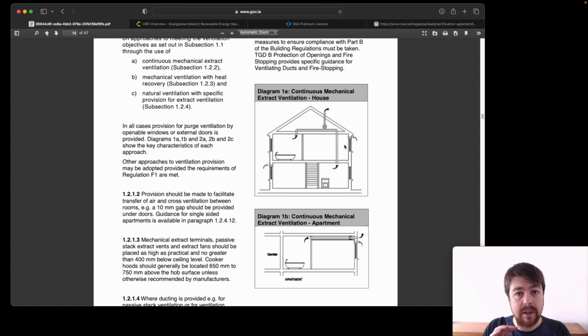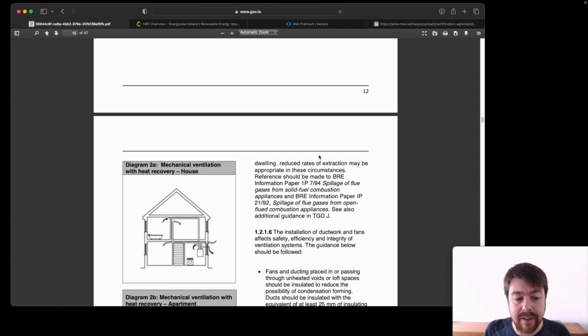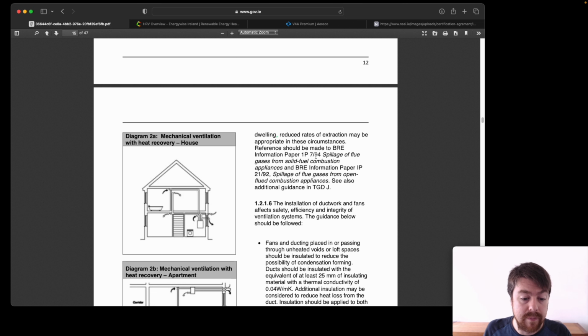But I want to do something a bit smarter, and for that I want to look at a mechanical heat recovery ventilation system. The idea, quite similar to what you'd see in a lot of North American homes, is to have internal ducting not just for the extract but also for the supply into the space. This ensures you get the right amount of air in and out of each space — a so-called balanced system. You can also, when sucking air out of the space, try to recover some of the heat from that air and pass it to the incoming airstream.